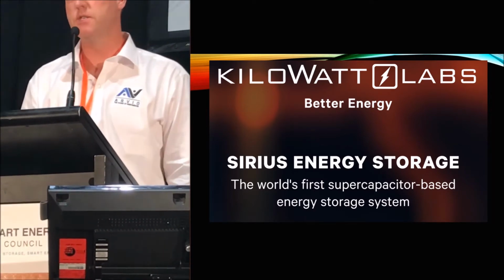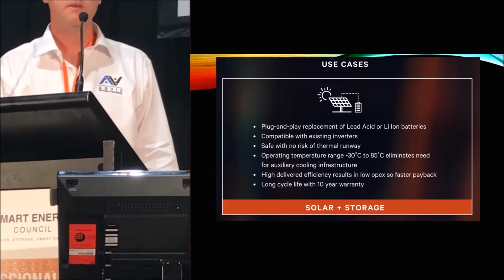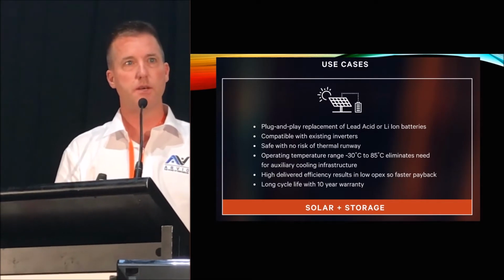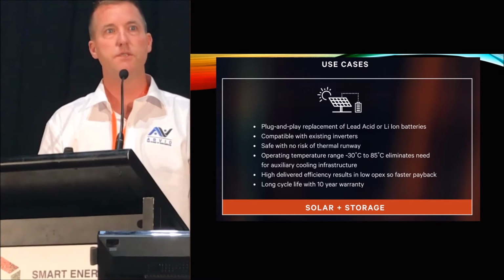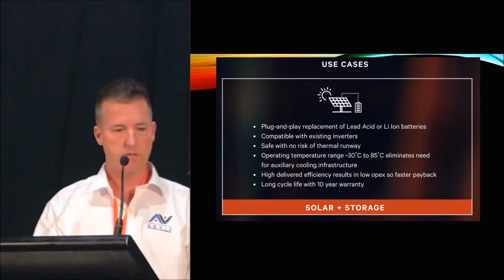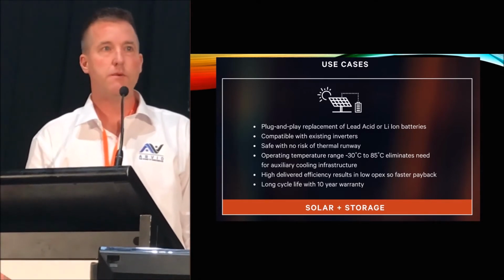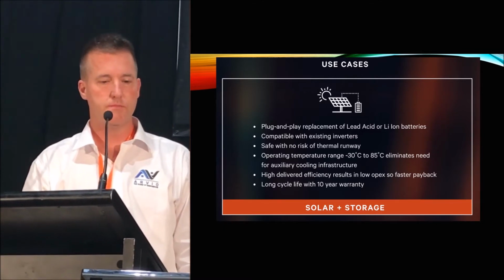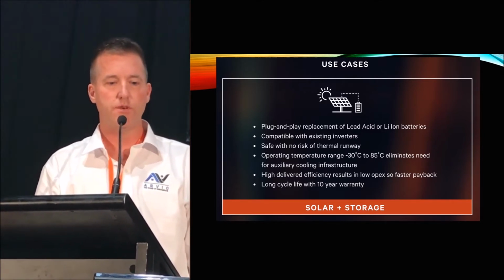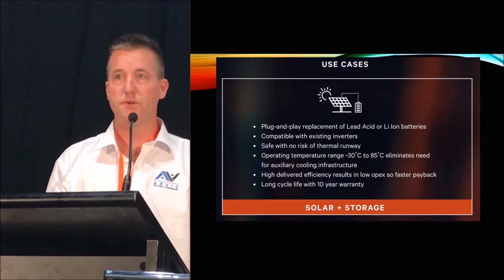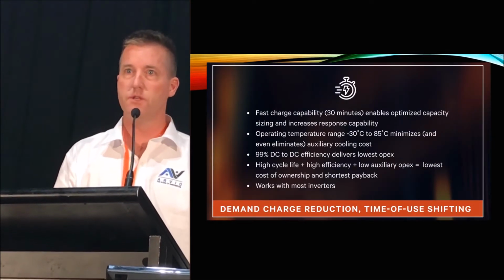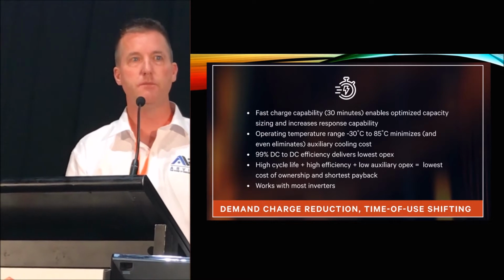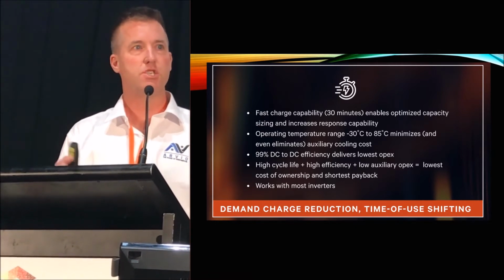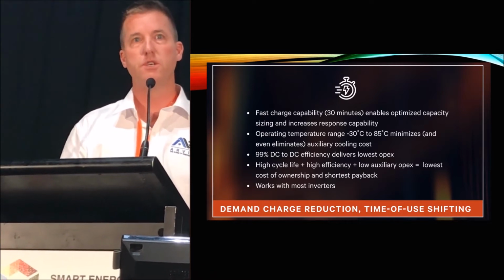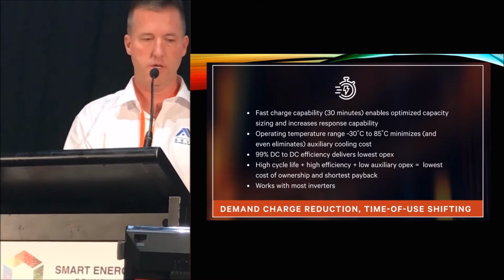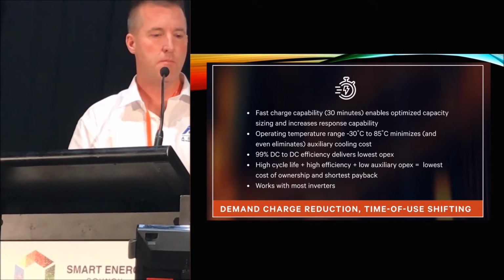The temperature operating range is up to 85 degrees at the cell level, but we recommend you design around keeping it above -10 and below 55 degrees just to get the best life out of the electronics. It's a 10-year warranty with unlimited cycles. You can charge in 30 minutes. It's 99% round trip efficiency at the cell level and 96% tested at the terminals. That's our own independent testing, by charging and discharging 14 times for an entire day and looking at the average loss, not the best case.